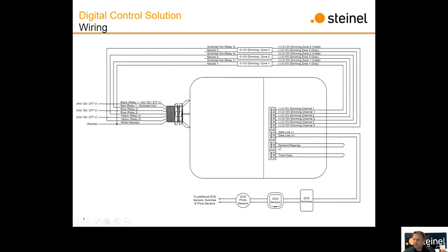We've also got the demand response input in here, which is essentially just a dry contact closure input, as well as what we call here, this is a port for an external time clock. If there is already a time clock in place, for example, on a BMS system or some other time clock, we can take input from that time clock and use that to override all the other settings. That is not in place of the internal time clock. I repeat, there is a time clock inside the DCS, but this gives you the ability to override that with an external time clock, should that come up.